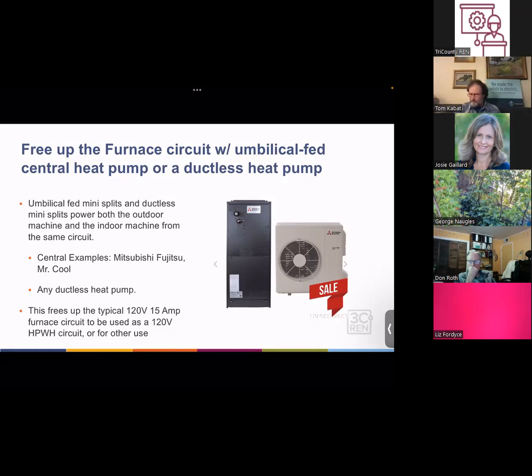Yeah, I can jump in here. So recovery time, I think, is the main thing. For the 240-volt water heaters, they have a resistance heater that's sort of like a backup. Let's say your heat pump's been running for 3 hours, it's gotten the tank from totally depleted to, let's say, 110 degrees, but it's not up to 120. And suddenly the users need a lot of hot water. That resistance coil will kick in. The 120-volt water heaters do not have that resistance coil.